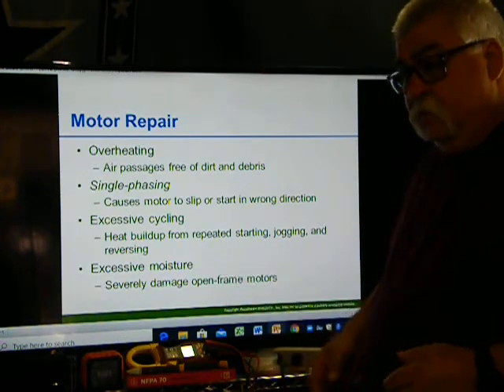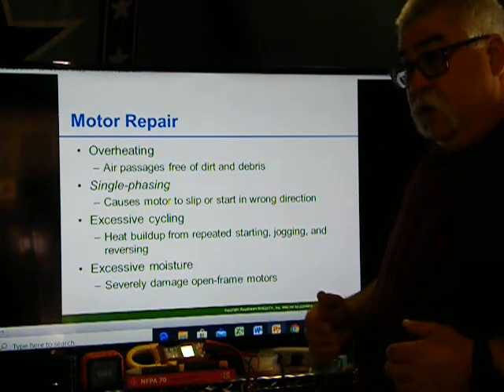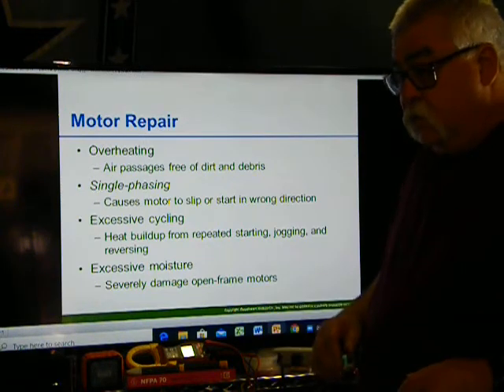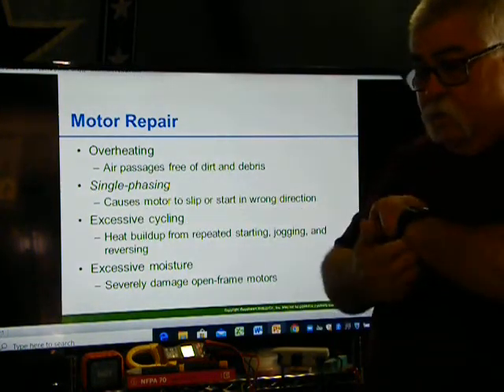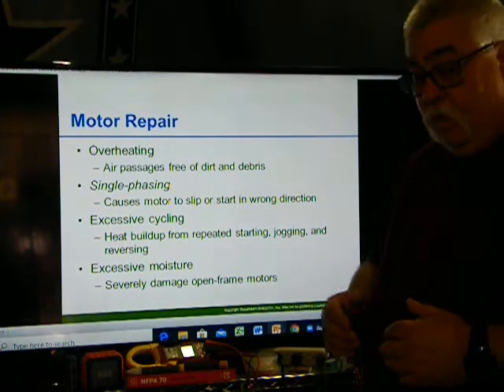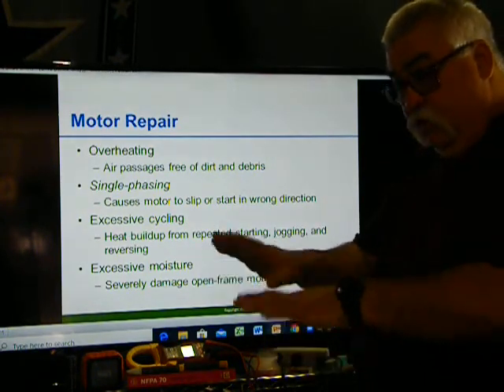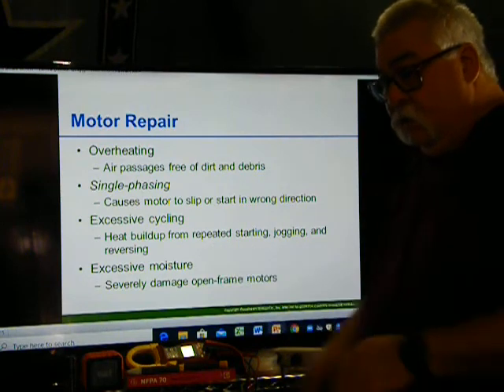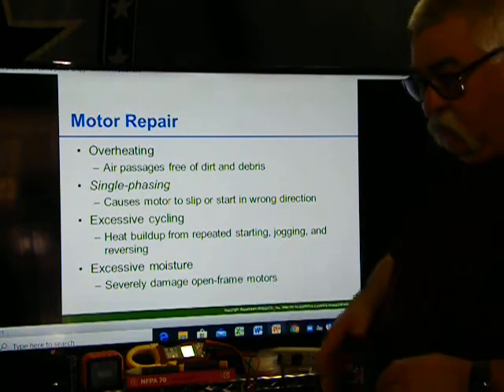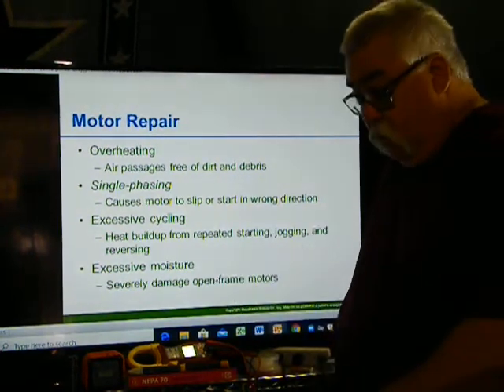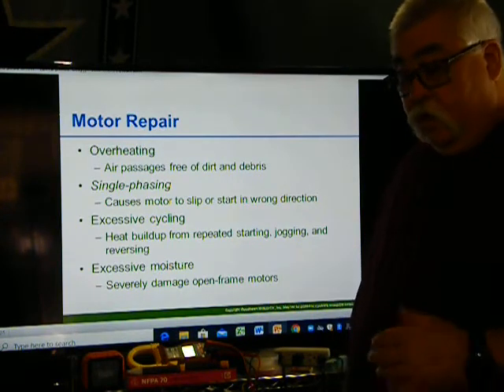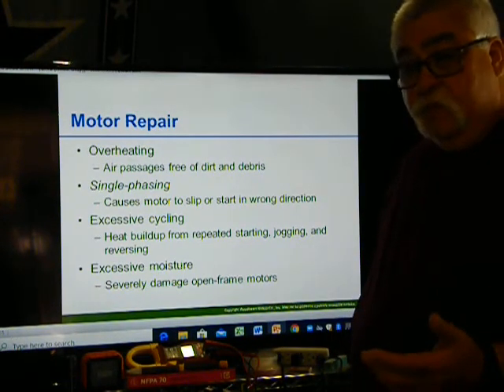We had another one, same thing. That machine ran 12 hours a day, and to get to that motor, you have to take 3 motors apart. Because of the way the conveyors work, you have to sit there and balance everything out. The limit switches and everything else have to be put in order to make sure it was running right. So it can take up to 4 hours to change the motor and get it going.